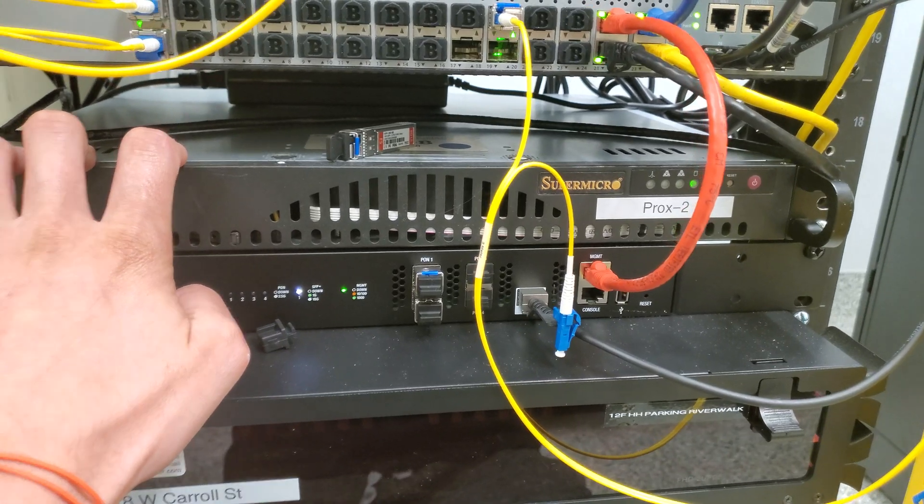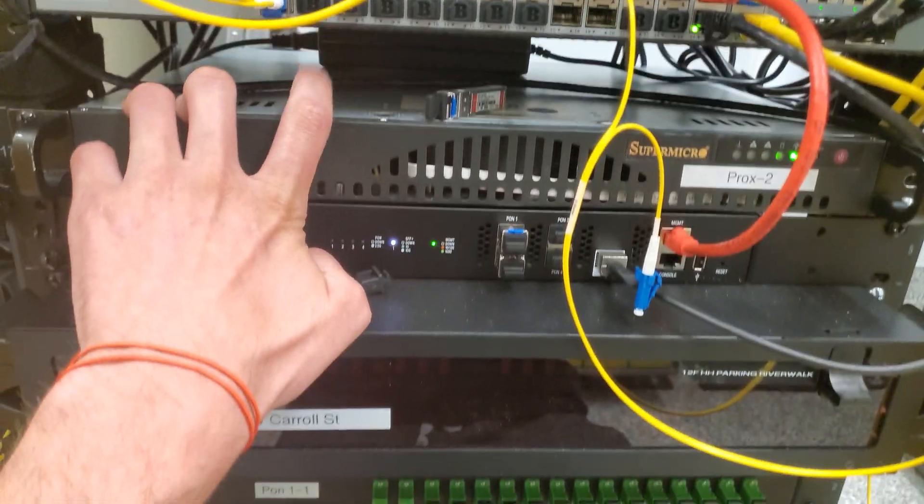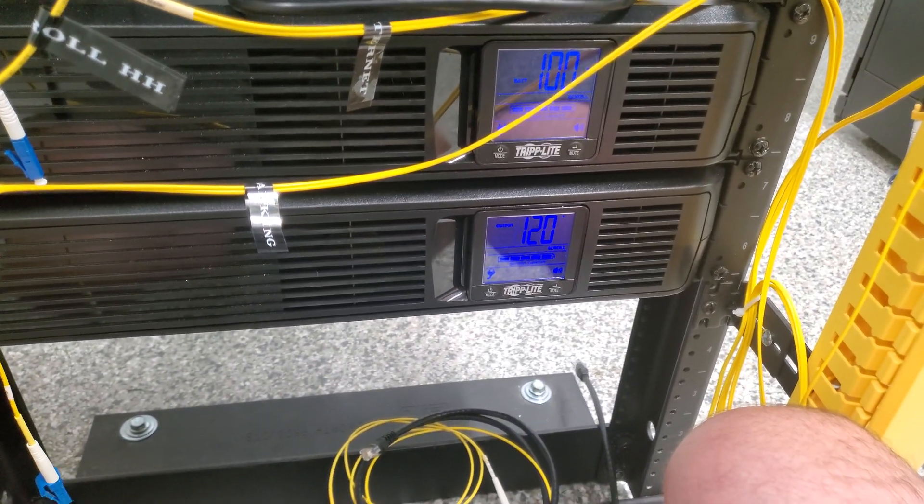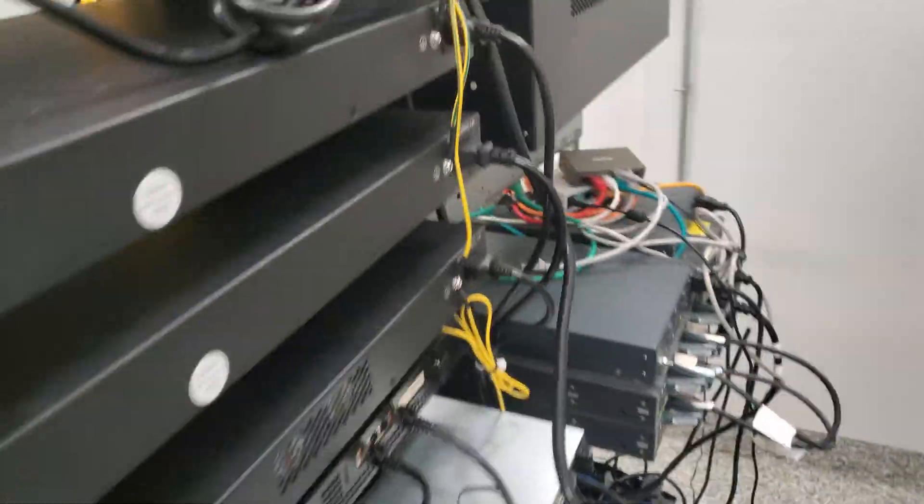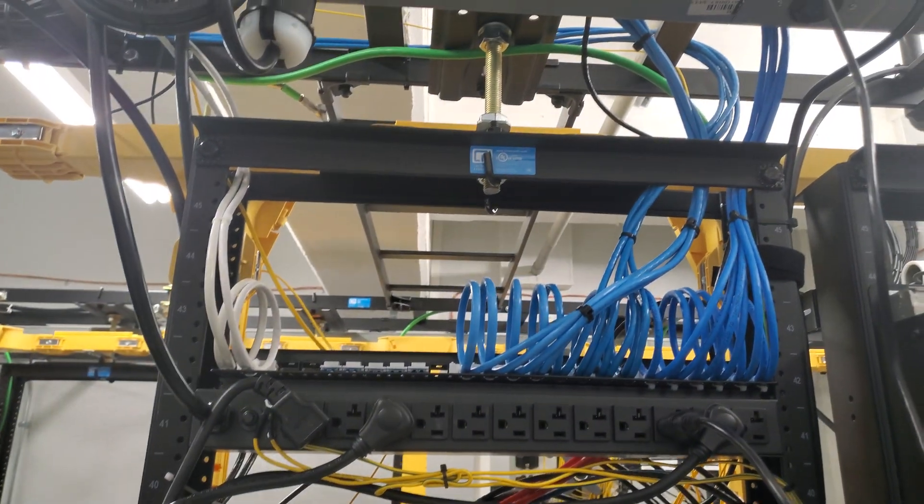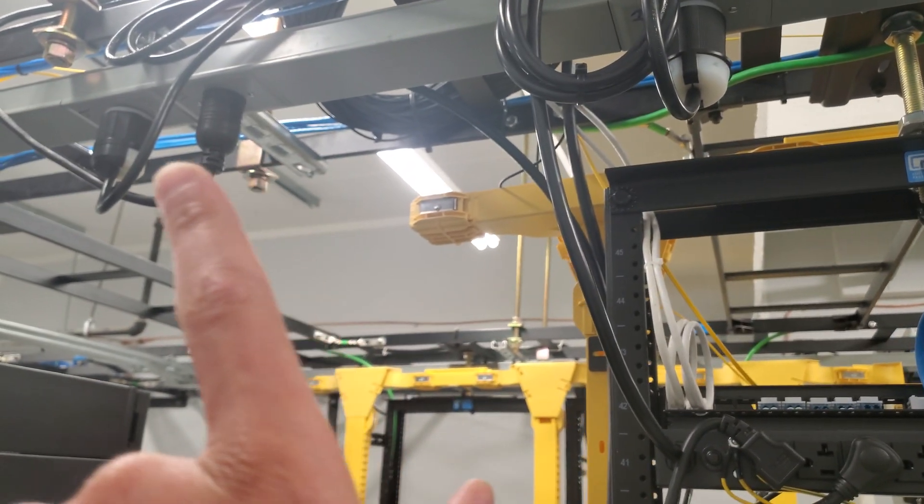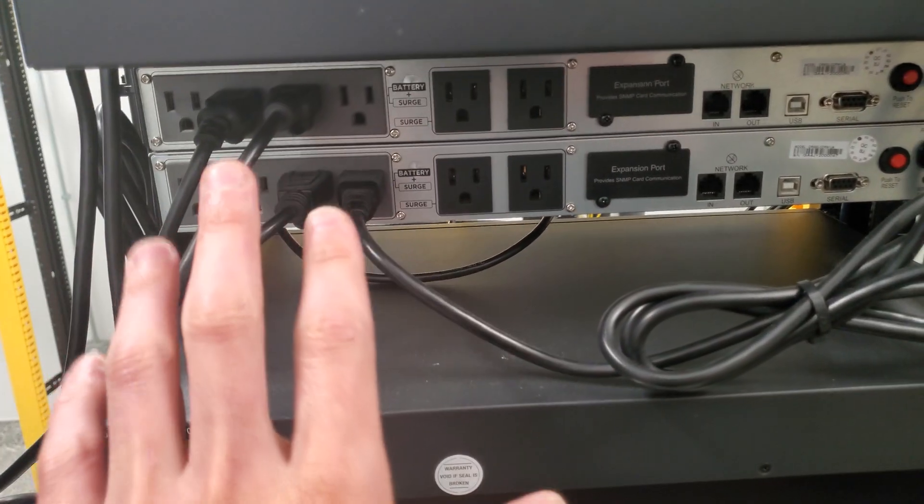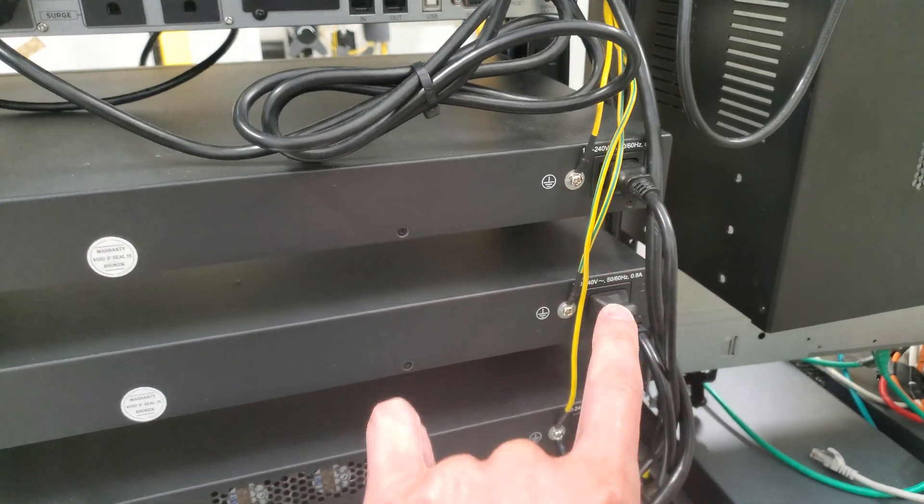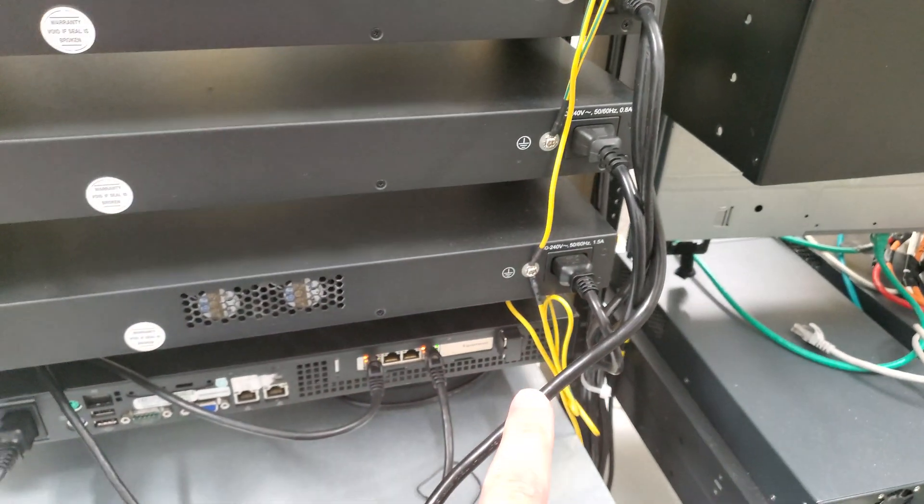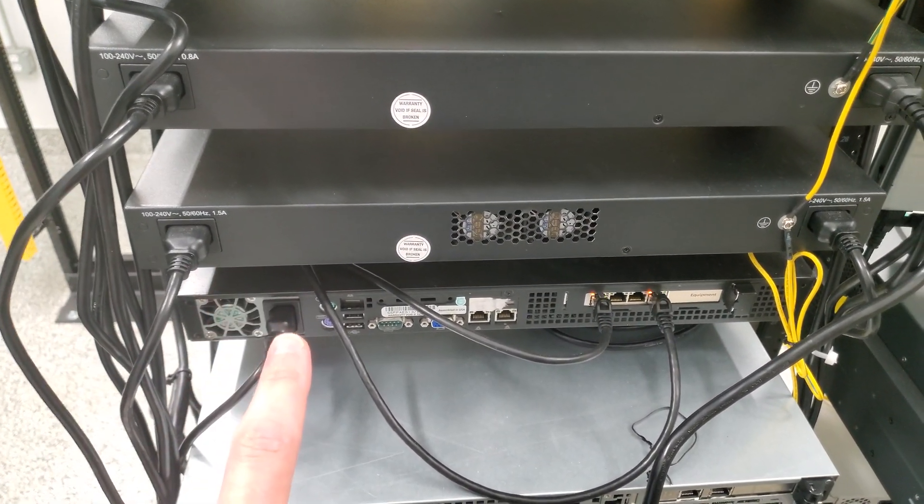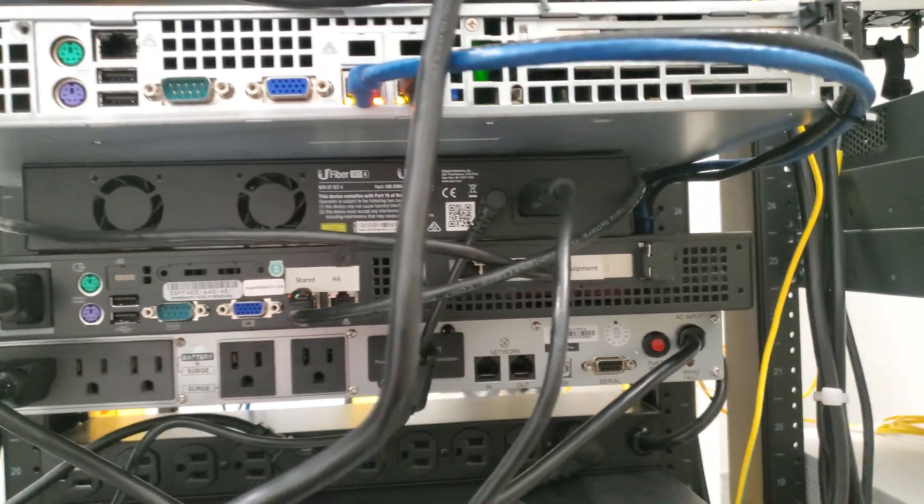Just some off-the-shelf batteries, nothing weird with the batteries. It works for us. Two of each battery stack. If you look at our switches, there's two phases coming in, and they're dual powering. So these two items are two different phases, two different circuits. If we lost a phase, we are still in business.